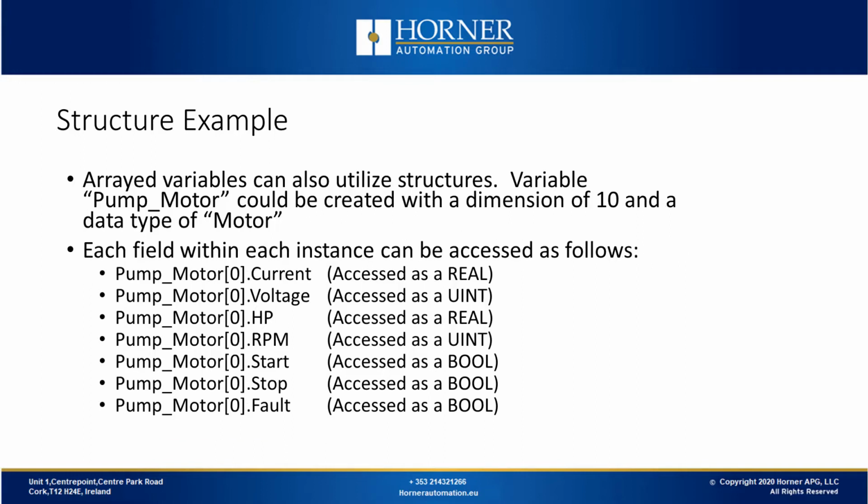You can also use structures with arrayed variables. So we'll create a variable called pump motor with a dimension of 10 and data type of motor. Now we have pump motor sub 0 through pump motor sub 9. Each field within each instance can be accessed as seen on screen.